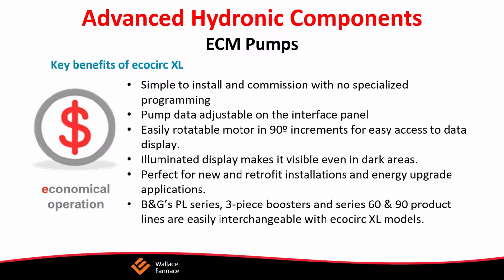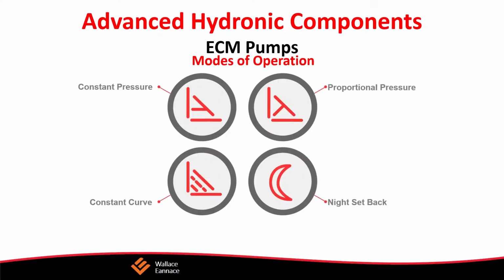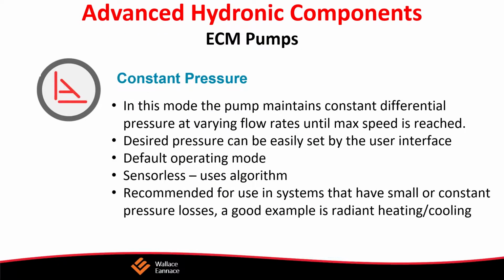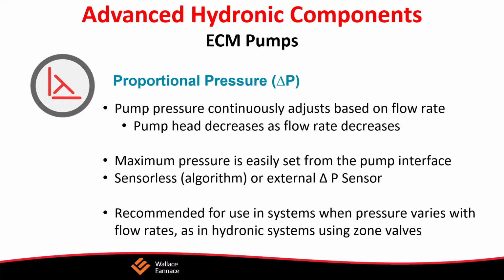Taking a look at the internals of this pump, what you see here is that it comes with the self-flushing membrane. It restricts abrasive particles. There's a high temperature EPDM O-ring and a stainless steel shaft. The pump housing will either be cast iron or lead-free or stainless steel. All the wetted parts are 304 stainless steel. So once we change the volute, the unit's already a stainless steel device ready for potable applications. The impeller is glass-filled polyphenylene sulfide, or it comes with 316 stainless steel, depending upon the unit.